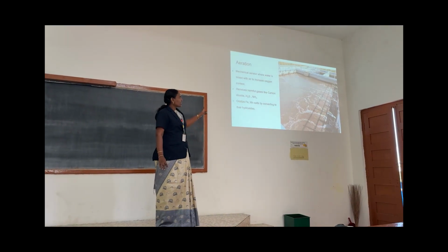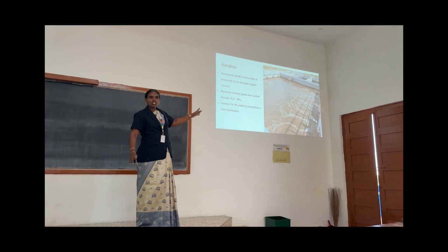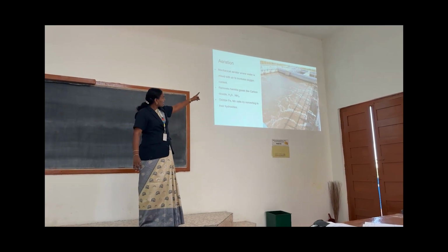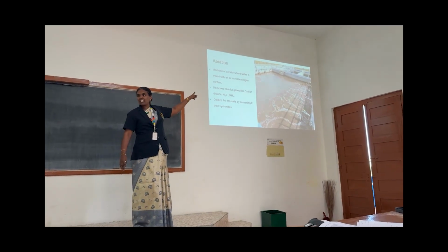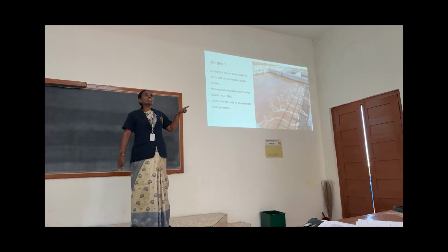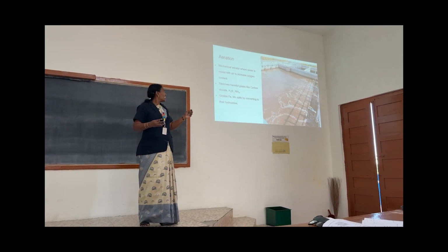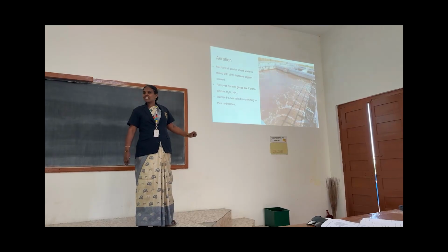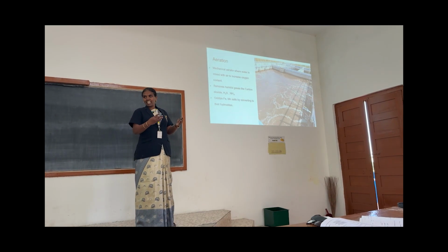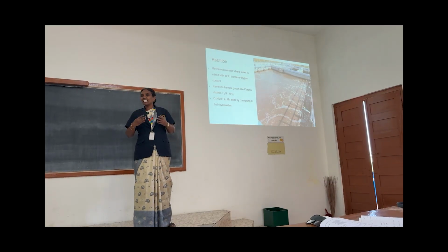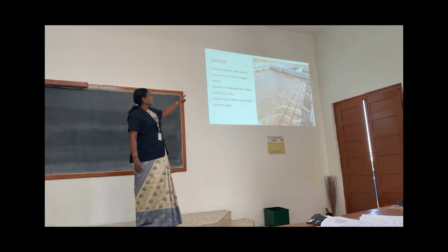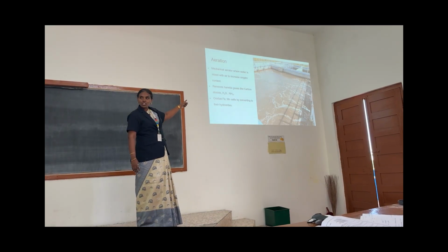Then next, aeration. See the picture. Such a huge water area we are covering. In that water we are passing air. Aeration means we have to pass air. If we are passing air, what will happen? It oxidizes. It increases the oxygen content. What is its use? It removes harmful gases like carbon dioxide, H2S, NH3.